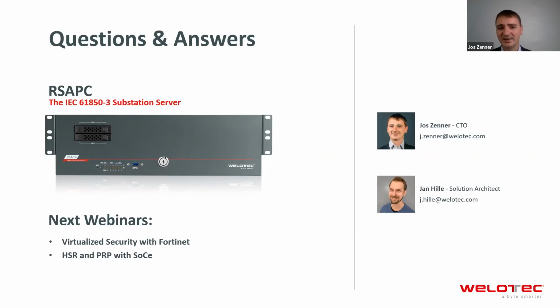So there is definitely a CAPEX reduction. And if you're looking at the OPEX reduction, imagine what happens if you have 5 different devices in a substation, so hardware devices. So you need to maintain this hardware. You need to make sure that you have spares. In case one hardware fails, you need to physically replace it right away. So with virtualization, you can just do that virtually. So you just move one snapshot, so one, for example, firewall, from one computer to the other.